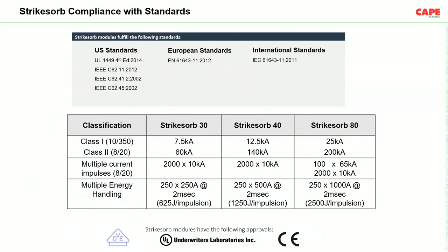Now, this is one of the major important advantages that bus bar mounted SPDs have over other SPDs. All these SPDs are tested with VDE as well as UL 1449 fourth edition. Now, in class 1 SPD, Strikesorb 30, even the least rated SPD is tested with 2000 surges of 10 kiloamperes each. Normally, a DIN rail SPD is tested with maybe 10, 15, 20 surges. Their testing method is, once a surge is given to a DIN rail SPD, it is allowed to cool down before giving the second surge. But practically, lightning is not going to wait for the equipment or SPD to cool down.